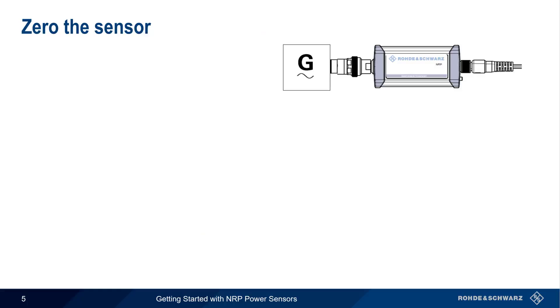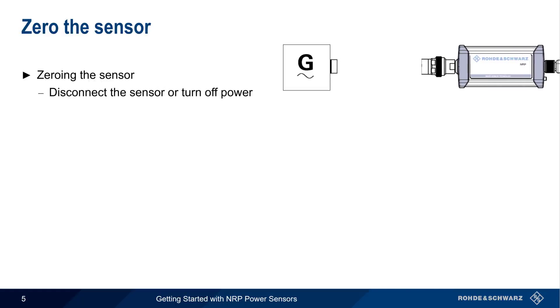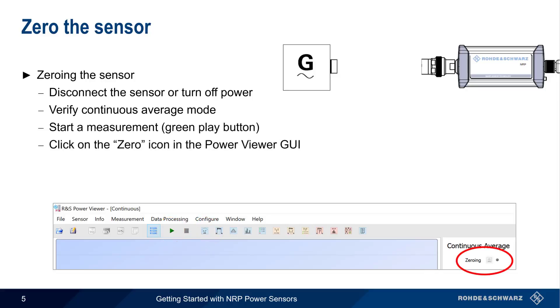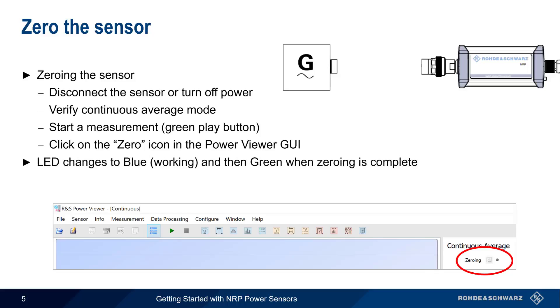Once the sensor is attached and recognized, the next step is to zero the sensor. To zero the sensor, first either physically disconnect the sensor from the device under test, or ensure that the device under test is not producing any RF power. In Power Viewer, verify that Continuous Average mode is selected and start the measurement using the green play button. Then click on the zero icon in the Power Viewer GUI. The LED should turn blue to indicate that zeroing is underway, and then green when zeroing is completed. This usually takes less than 10 seconds, but will depend on the sensor type.